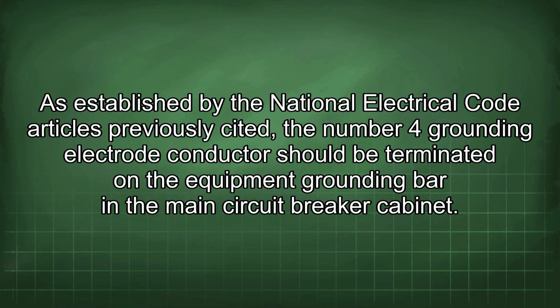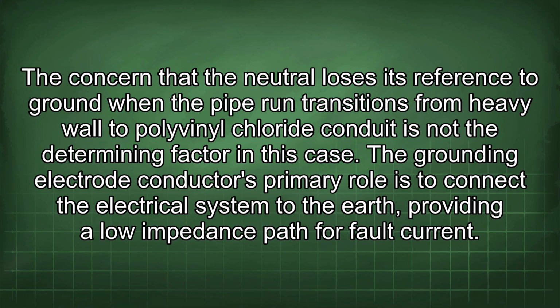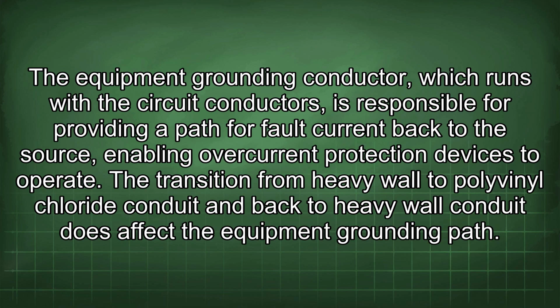As established by the National Electrical Code articles previously cited, the number 4 grounding electrode conductor should be terminated on the equipment grounding bar in the main circuit breaker cabinet. The concern that the neutral loses its reference to ground when the pipe run transitions from heavy wall to polyvinyl chloride conduit is not the determining factor in this case. The grounding electrode conductor's primary role is to connect the electrical system to the earth, providing a low impedance path for fault current. The equipment grounding conductor, which runs with the circuit conductors, is responsible for providing a path for fault current back to the source, enabling overcurrent protection devices to operate.